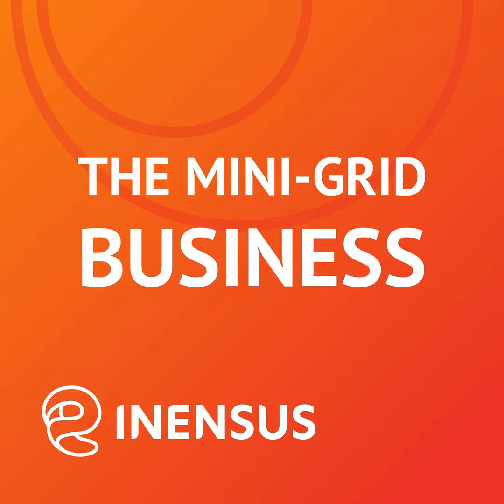2 villages. In Africa and Asia and developing countries in general, you don't build the distribution networks with a lot of redundancy. In Europe, for example, we have a lot of meshed or ring type of networks where if one string fails, then the other string can take over the entire supply to the end customers. This also helps in maintenance. You can, for example, switch off a certain part of the distribution network without disconnecting the end customers from the network. This, however, also means that both lines, both angles of the ring need to have the full capacity to transfer the full amount of electricity to the customers, which means way too much capex for a developing country. You want to keep costs down.